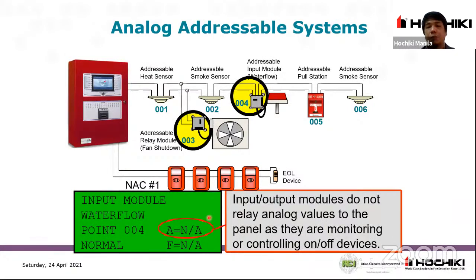So input-output modules do not relay analog values to the panel as they are monitoring or controlling on-off devices. Ayan. So kapag modules lang tayo, ito is on-off lang. So meaning, for example, itong water flow, pag nag-activate siya, magbibigay lang siya ng signal dito sa input module natin na magbibigay doon sa panel. So wala naman siyang sensitivity level, on or off lang for the modules. Okay? So ayun yung mga information natin for the analog addressable system.